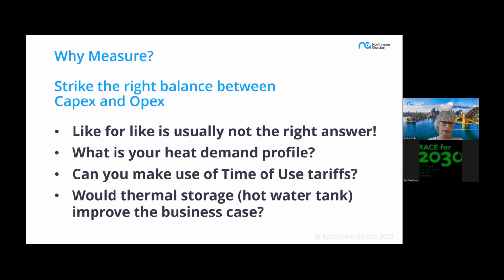And the way you would do that is using thermal storage. And thermal storage can be used to improve the business case. It can minimize the size of the system that you need to install. And it can also enable you to make use of time of use tariffs and also demand reduction activities and that sort of thing. So it's very useful to be able to do that. And to do that, you need to be metering your system before you design your heat pump system.